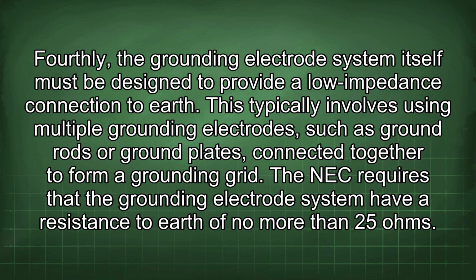This typically involves using multiple grounding electrodes, such as ground rods or ground plates, connected together to form a grounding grid.